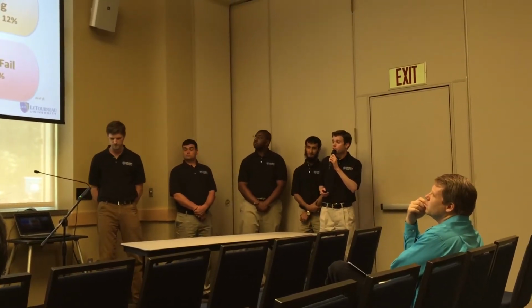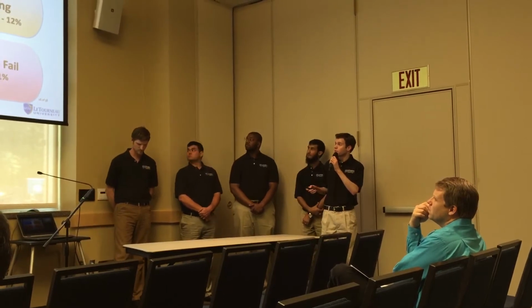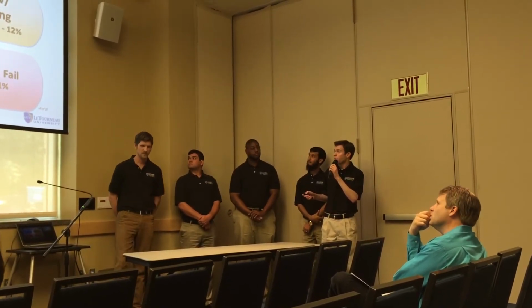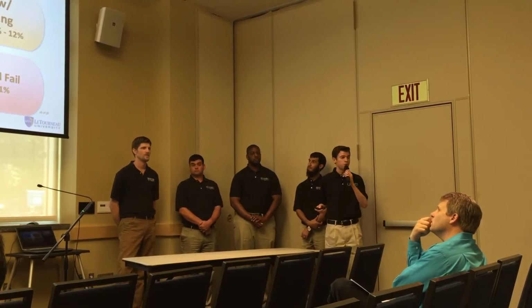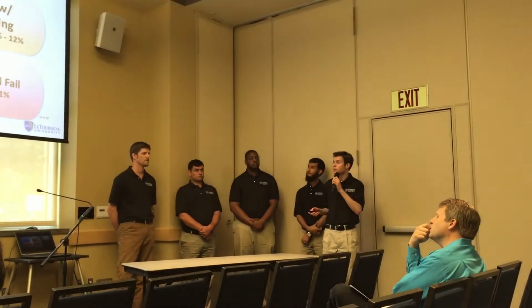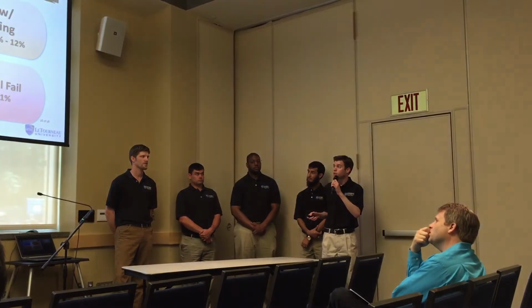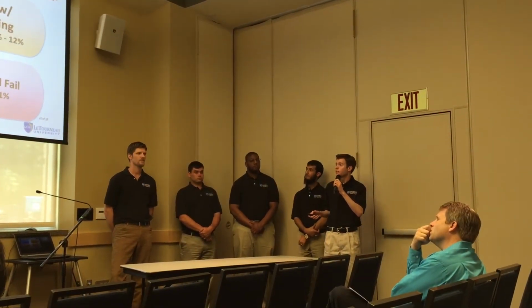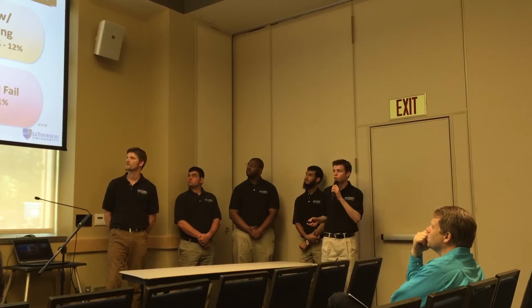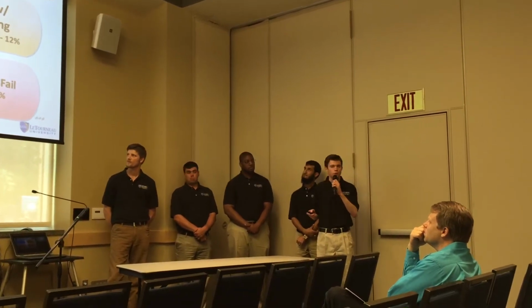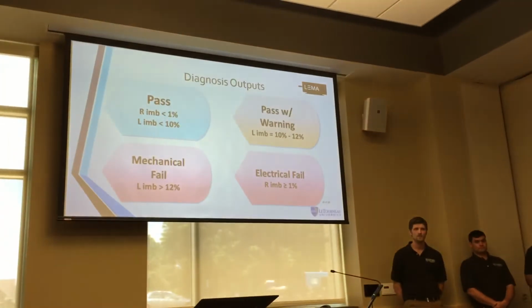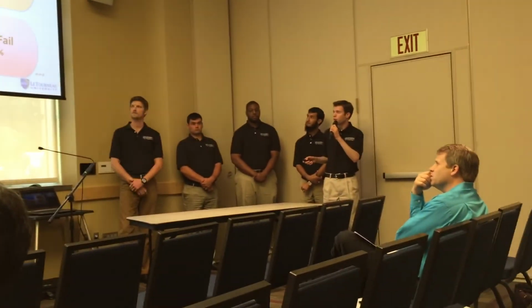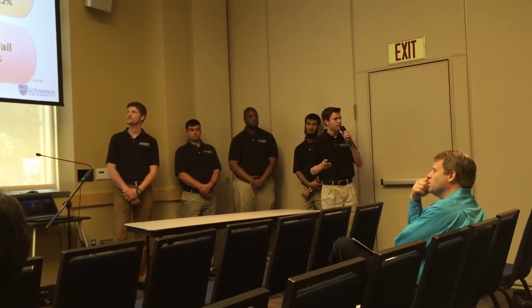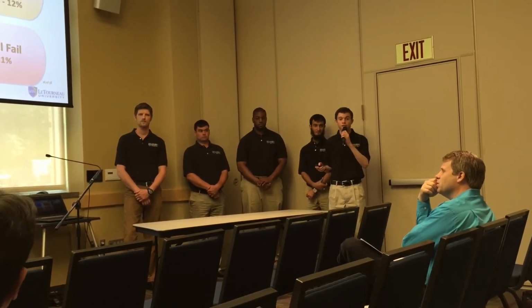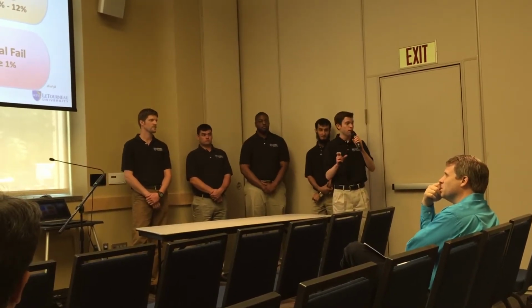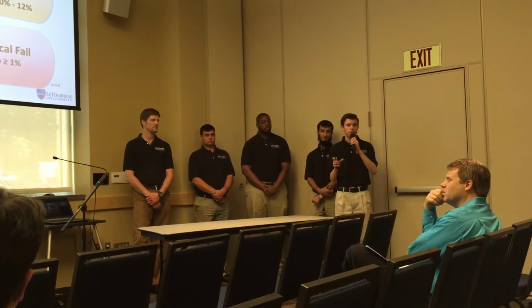Our device outputs basically 4 results: the motor will pass, pass with a warning, or fail, based on one of two tests we run - either the inductance imbalance is too great, or the resistance imbalance is too great. These are the thresholds indicated to us by Flanders that determine whether it's a failing motor or not. One of these 4 outputs is displayed on our color display, easy to read and understand. If it's a failing result, it will display the values of how much it failed.